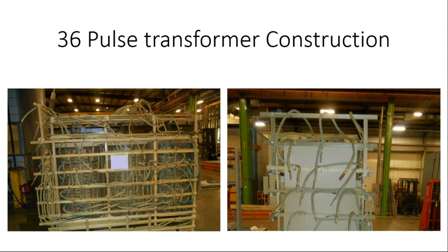On the HV side, it's not that difficult. Mostly they are in the Y or delta configuration with a DETC tap changer, 5, 7, or 9 taps, which is very common for such applications. Most of these transformers do not need any regulation or a load tap changer. At least we have not seen any multiple pulse transformer with a load tap changer, because they have the choice to change the voltages with the rectifiers.